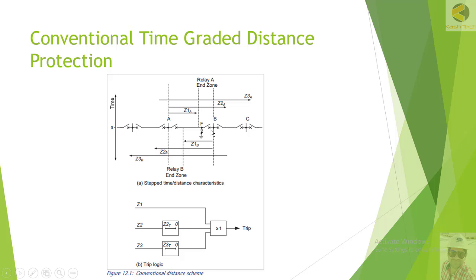However, for cases where, for example, breakers fail at station A and this cannot be checked at station A, or if there is high voltage at station B due to ferranti effect or similar effects that cannot be checked at station A — in such cases where it is inherently not possible to apply a condition or pre-check at the remote end, the direct transfer trip scheme is used.